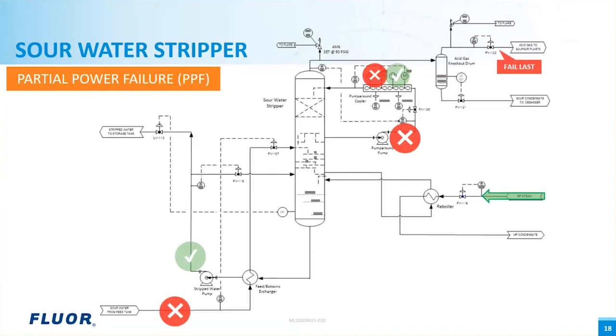Typically, power to pumps and fans is supplied by two independent substations — bus A and bus B. The consequence of one substation failure, either bus A or bus B, has been analyzed. The worst case scenario, which is the bus B failure here, is taken as the partial power failure upset event.